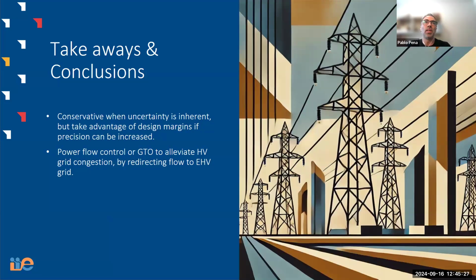Be conservative when uncertainty is inherent in the problem, but take advantage of design margin if you can increase the precision, for example, using LIDAR and a digital twin. And finally, power flow control or GTO to alleviate high voltage grid congestion. It's a good idea by redirecting flow to the extra high voltage grid, as in the case of Uruguay. But depending on the case, you may need some new infrastructure, new lines, or to mesh the grid.